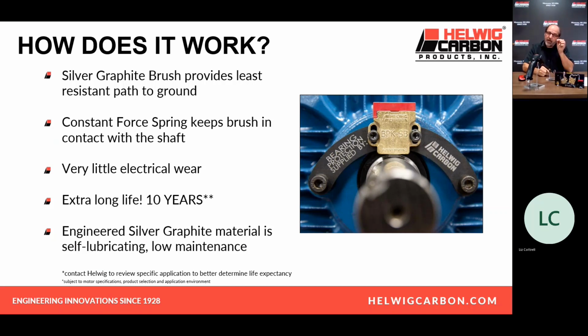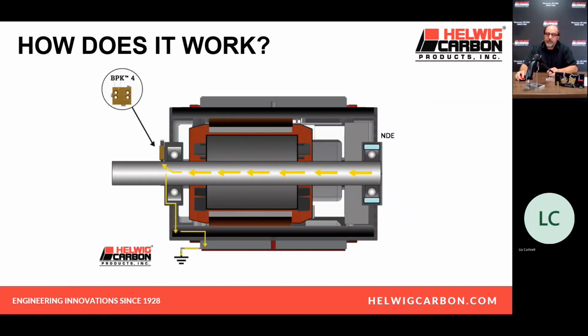It puts a conductive layer down. That conductive layer, some people might say, well, you don't want a layer on there because that adds resistance. Not if it's a silver graphite layer. It actually is a conductive film we put down, which adds a lubricant, which even increases the brush life more. That's all part of our K007 grade and part of the magic that's in there.